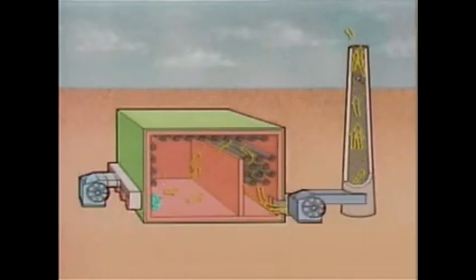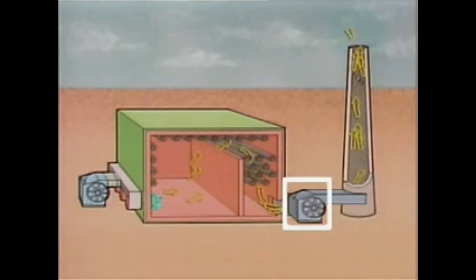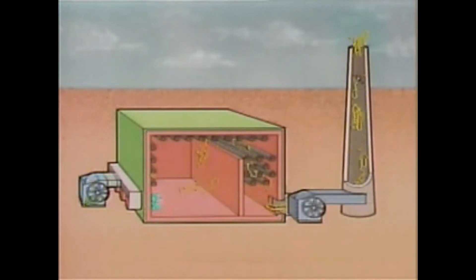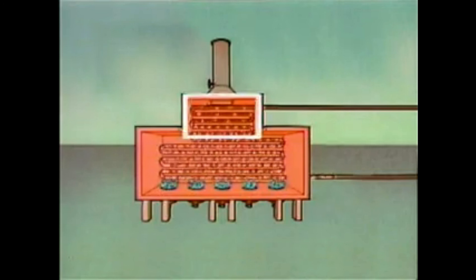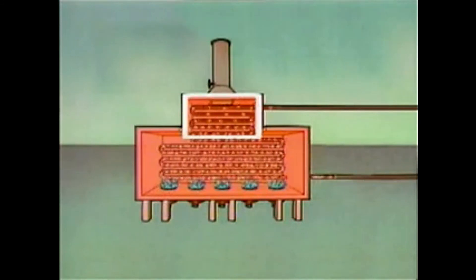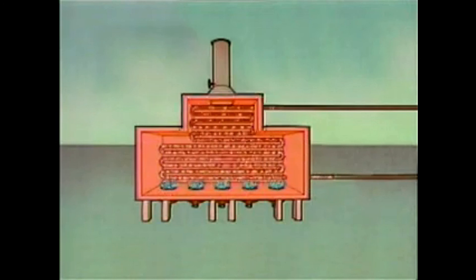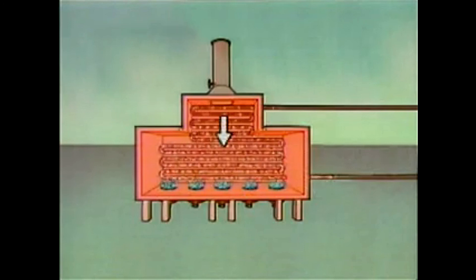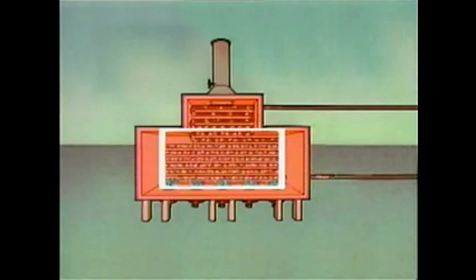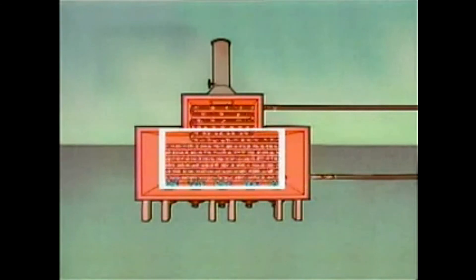A balanced draft furnace is similar to a force draft furnace but has an additional induced draft fan located in the flow path of the combustion gases between the furnace and the stack. One fan provides air for the burners and the other removes the combustion gases. In this floor-fired furnace, the process fluid enters through the tubes in the convection section and is preheated by the combustion gases before reaching the radiant section, where it becomes hottest due to the higher temperatures available.